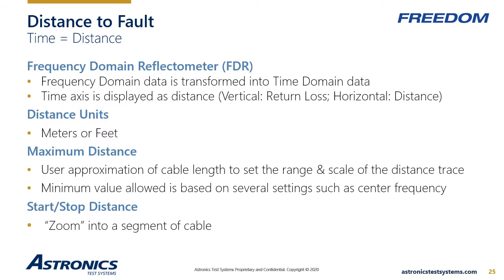The FREEDOM R8200 VNA's distance to fault tool is a frequency domain reflectometer, or FDR. This is a sophisticated tool which provides major improvements over the older time domain reflectometer, or TDR, which used DC pulses and were primarily used to locate catastrophic failures such as opens and shorts in your cables. The FDR sweeps the cable over its operational frequency range and measures the return loss. The data is then processed to present loss over distance.